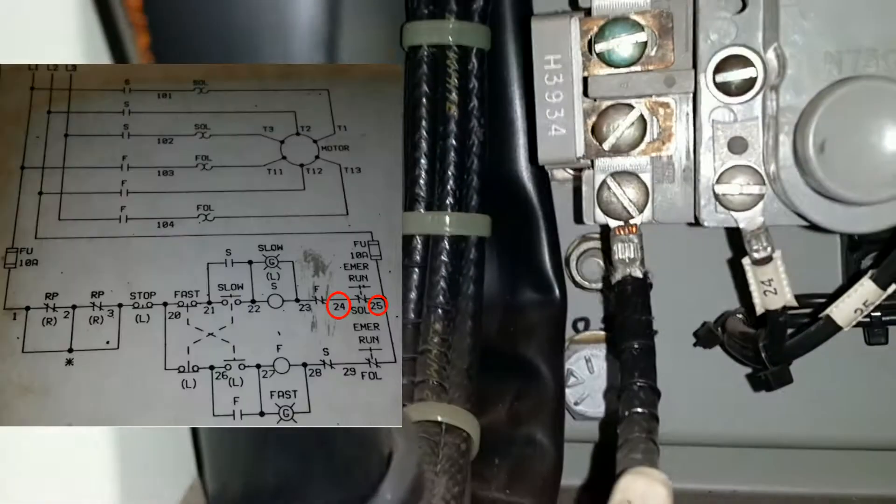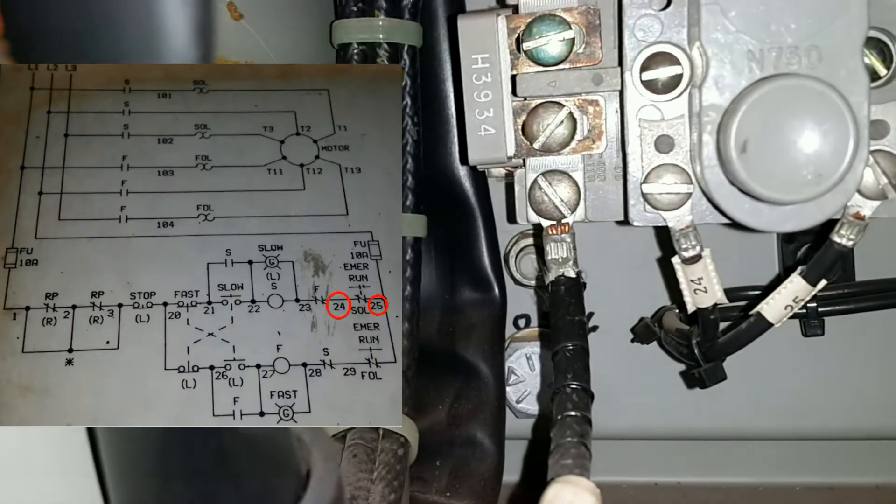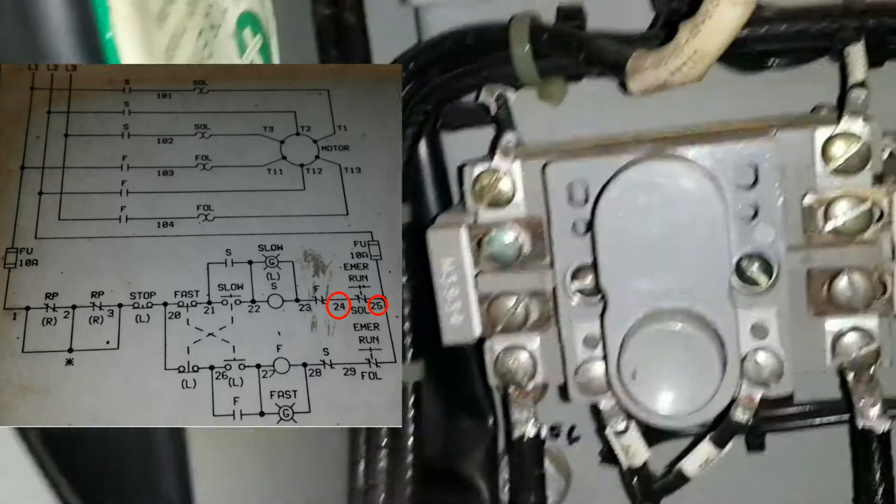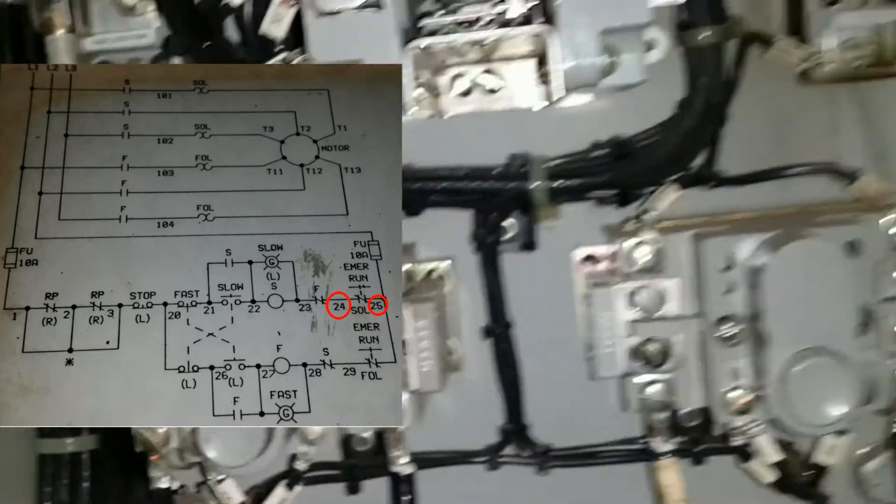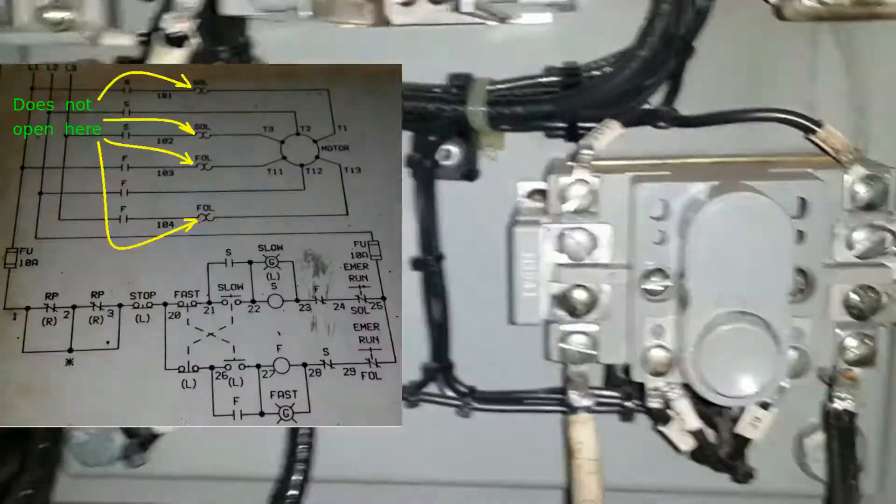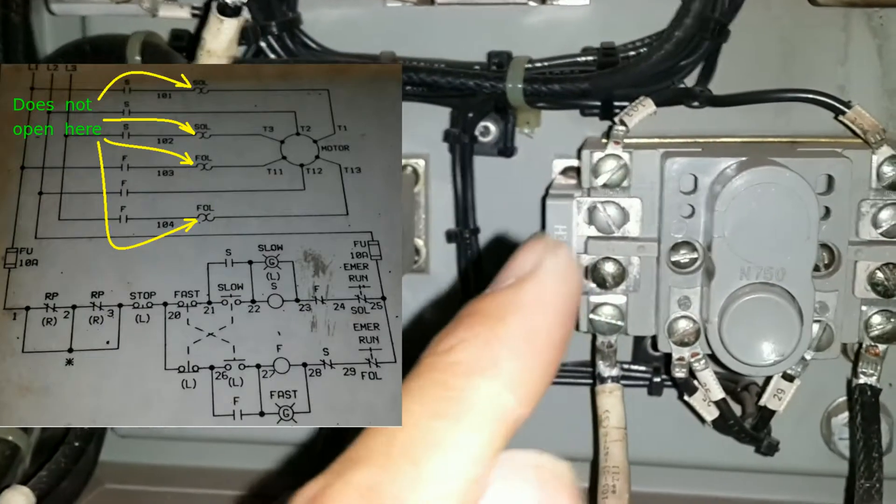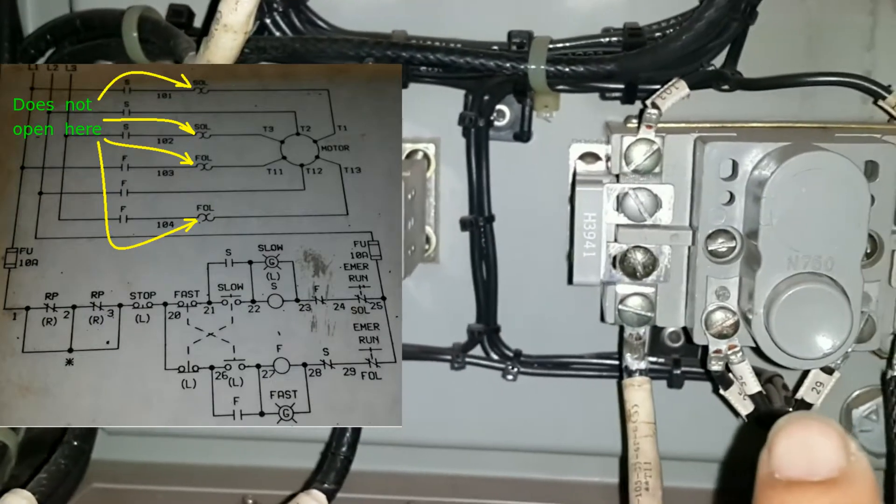And this is the low speed overload switch. Keep in mind that if the motor gets into trouble and it starts to get too hot, this is not what opens. What opens is the contacts that are here and there.